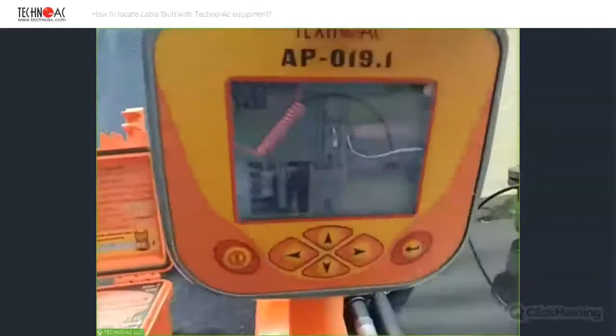So, what is an A-frame sensor? The A-frame sensor is a two-conductor sensor which evaluates the electric potential difference between these two legs, and it can tell where the fault is exactly. So this device is used for pinpointing the fault in the cable. This sensor has extendable legs like this. And the distance between these two legs is 1 meter. So this is 1 meter length.